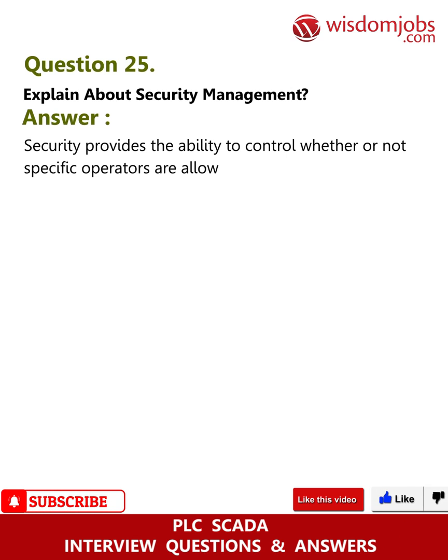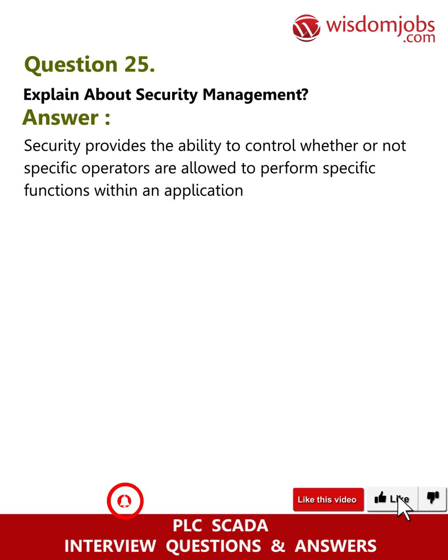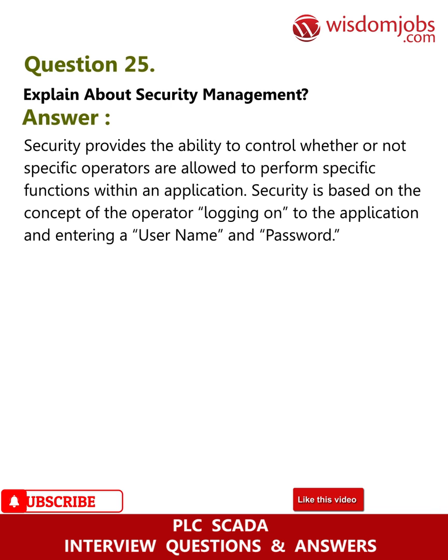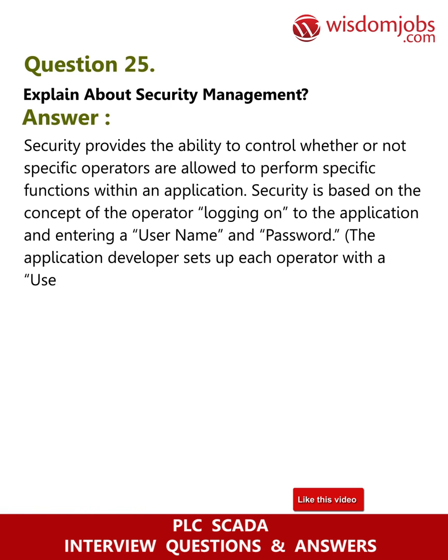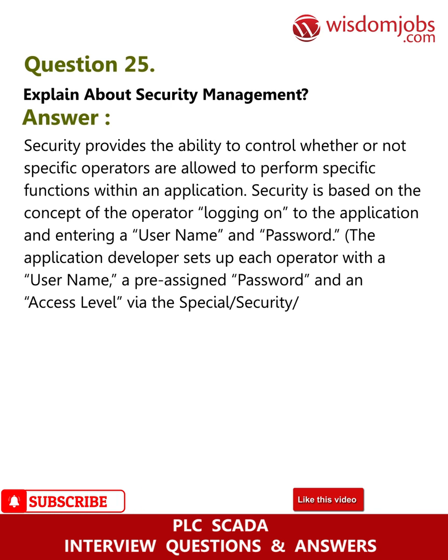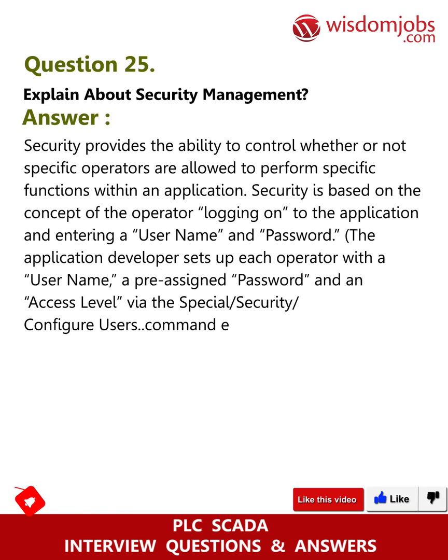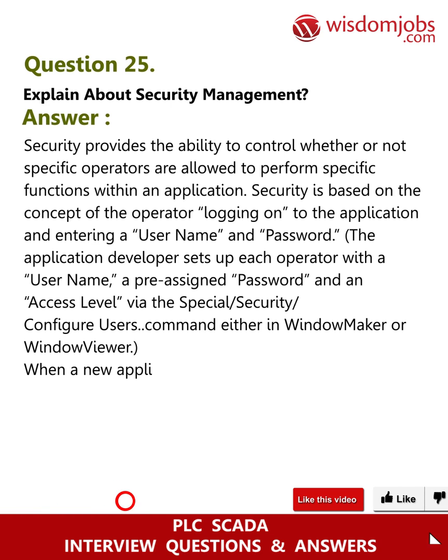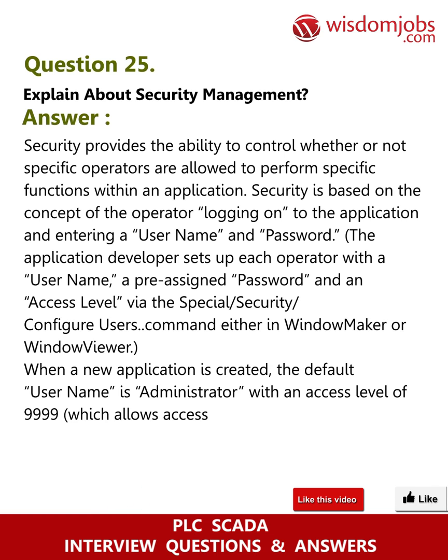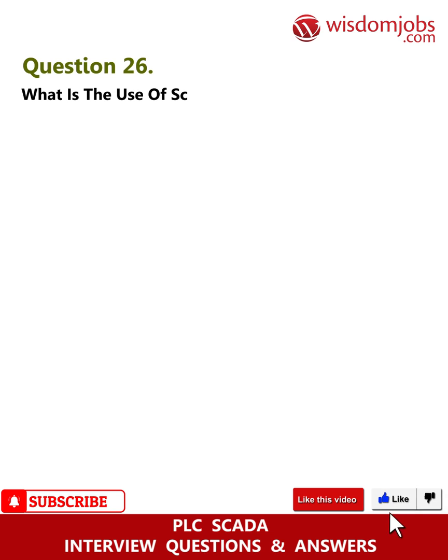Question 25: Explain about security management. Answer: Security provides the ability to control whether or not specific operators are allowed to perform specific functions within an application. Security is based on the concept of the operator logging on to the application and entering a username and password. The application developer sets up each operator with a username, a pre-assigned password, and an access level via the Special/Security/Configure Users command, either in Window Maker or Window Viewer. When a new application is created, the default username is 'administrator' with an access level of 9999, which allows access to all security commands.